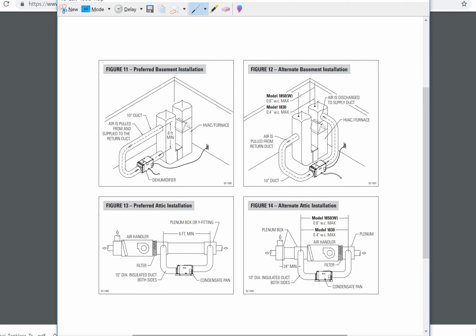So the purpose of this video is to talk about the preferred installation arrangement for a dehumidifier. And this diagram has over here on this side a preferred basement, which is really about the orientation of the air handler being upflow. So that could be in a mechanical room closet, in a garage, any place where the airflow is upflow, or an attic installation, which is pretty much just horizontal flow.